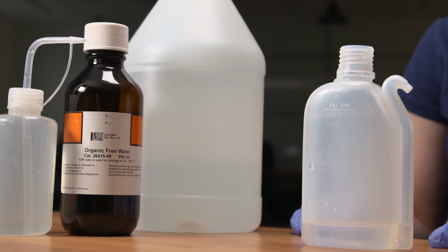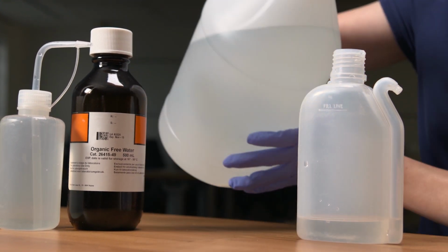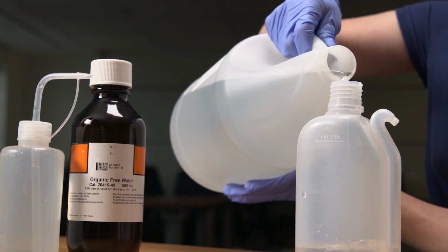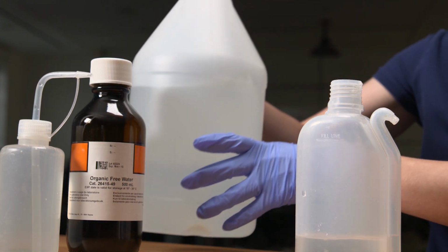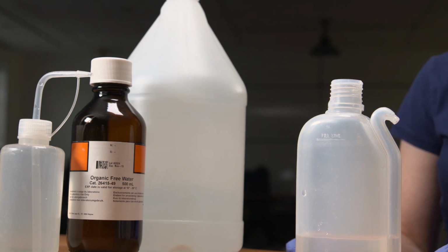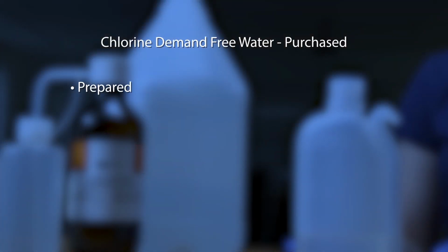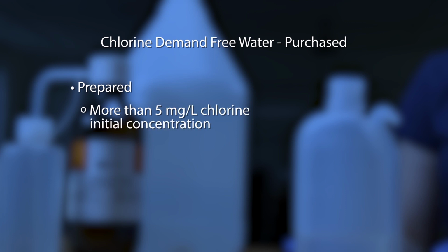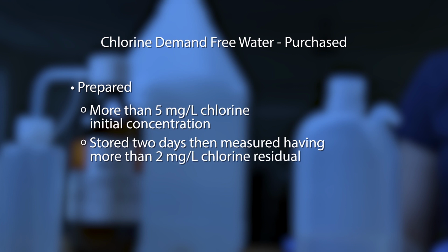Chlorine demand-free water can be used if a chlorine demand is present. Chlorine demand-free water can be purchased from scientific supply companies or the colorimeter instrument manufacturer, or it can be prepared. If preparing chlorine demand-free water, add enough chlorine to distilled or deionized water to give a 5 milligrams per liter residual. Measure the chlorine residual after 2 days. If the residual is greater than 2 milligrams per liter, then dissipate the remaining residual by irradiating with ultraviolet light and use once all chlorine residual is dissipated. If the residual is less than 2 milligrams per liter, then discard and obtain different purified water.